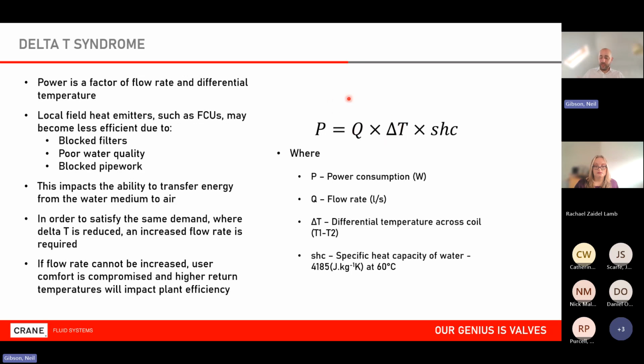Now, with a standard 0 to 10 volt control on a valve which has no delta T or temperature intelligence, it is purely going off the basis that it believes the position it's in is generating the flow rate it's designed for. When in reality, the flow rate may not be generating the power because the delta T is compromised. So it's one of these chicken and egg scenarios. I can't fix one without knowing the other.